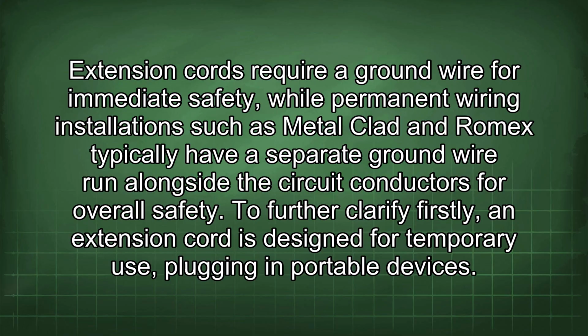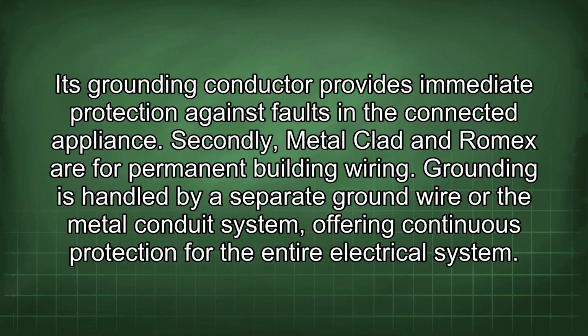To further clarify, firstly, an extension cord is designed for temporary use, plugging in portable devices. Its grounding conductor provides immediate protection against faults in the connected appliance. Secondly, metal-clad and Romex are for permanent building wiring. Grounding is handled by a separate ground wire or the metal conduit system, offering continuous protection for the entire electrical system.